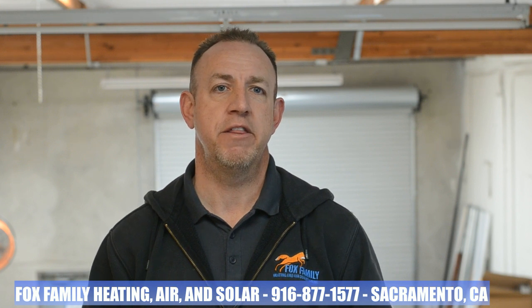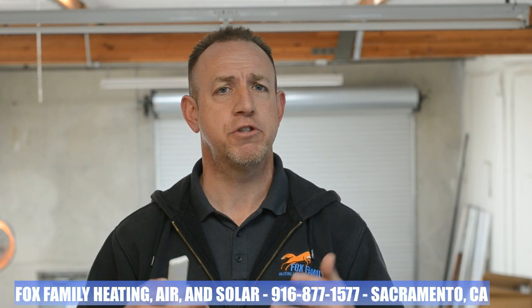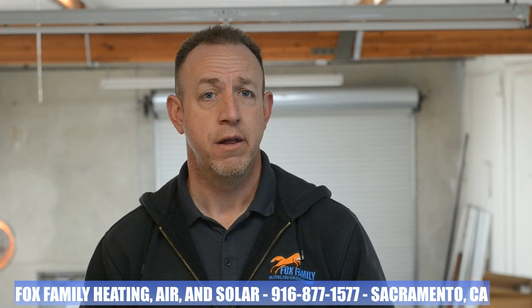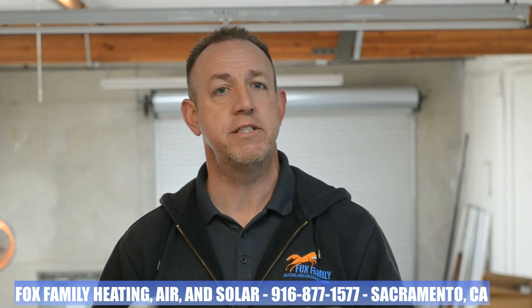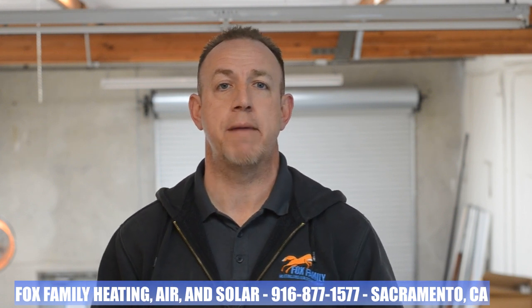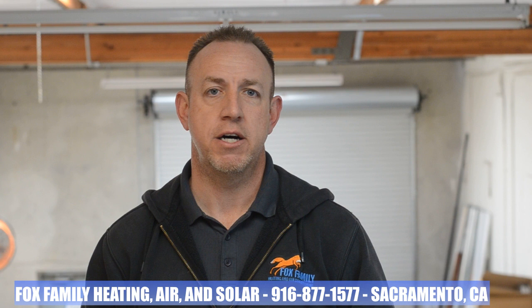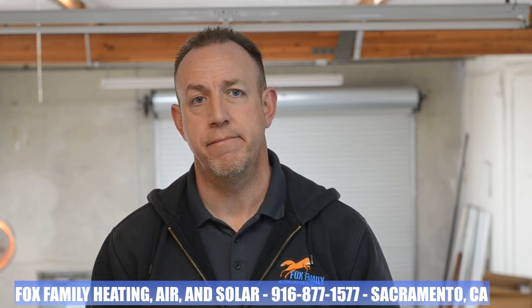Realistically, here in Sacramento, I think we should label ourselves as very unlikely to be affected by an earthquake. But we do service a wide region here at Fox Family, so the farther out from Sacramento we go, the greater the chance that the homeowner is experiencing effects of seismic activity. Therefore, we will continue to strap the units down to the decking in the attic and securing our AC to the pad that it sits on to prevent shifting. I hope this clarifies the part of the mechanical code that talks about why we need to strap our units to the ground. It may not come across as clear as other parts of the code, but it's legit. And if the inspector writes you up on it, now you know why.